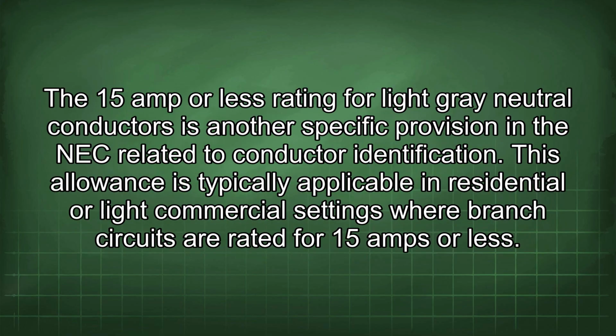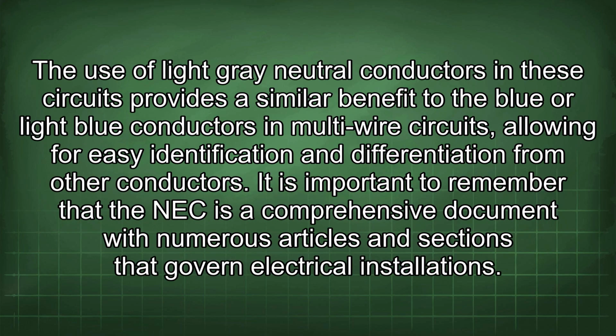The 15 amp or less rating for light gray neutral conductors is another specific provision in the NEC related to conductor identification. This allowance is typically applicable in residential or light commercial settings where branch circuits are rated for 15 amps or less. The use of light gray neutral conductors in these circuits provides a similar benefit to the blue or light blue conductors in multi-wire circuits, allowing for easy identification and differentiation from other conductors.